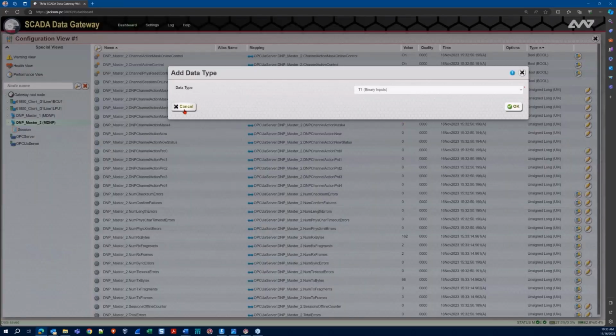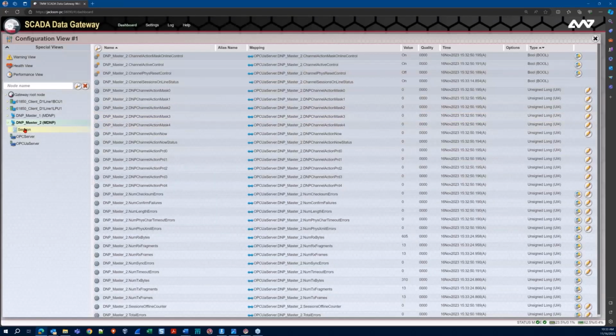This is where I would add the types of data points I want read into my DNP3 master. There are a couple different ways I could handle this. I could do a discovery, or auto-create tags. If my DNP3 outstation is out there and available on the network, it'll go out and do a discovery, asking what types of points exist on this device. It'll do a general polling of everything out there and create the appropriate tags here in my DNP3 master, and in some cases that might be exactly what I want to do.